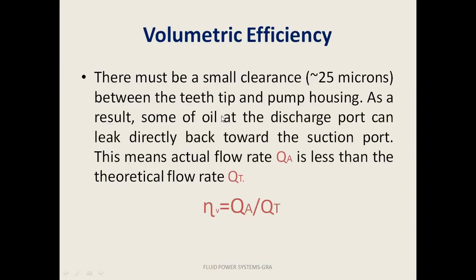Right? So there must be a small clearance, that is around 25 microns, between the teeth tip and the pump housing. This is what I told you while explaining the external gear pump. As a result, some of the oil at the discharge port can leak directly back towards the suction port. Because of this, the volumetric efficiency of the gear pump will be very less.